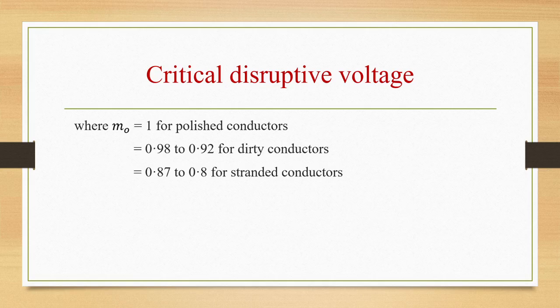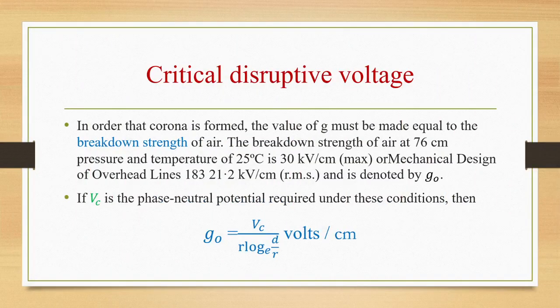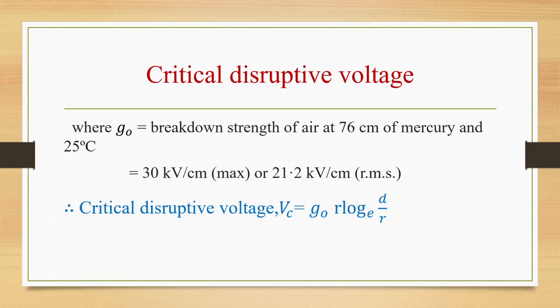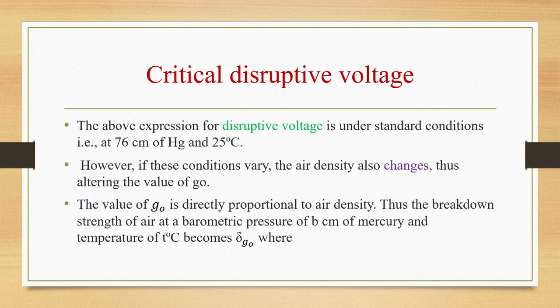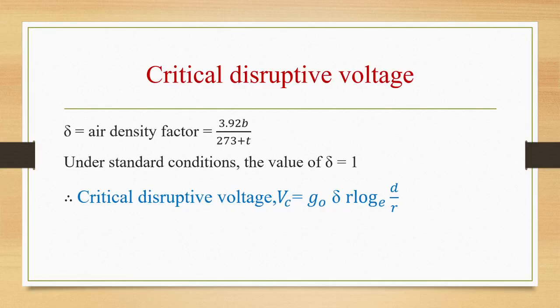If Vc is the phase neutral potential required under this condition, then g naught is equal to Vc by r log base e d by r. Here g naught is the breakdown strength of air at 76 centimeter of mercury and 25 degrees centigrade of temperature, and that is equal to 30 kilovolt per centimeter maximum or 21.2 kilovolt per centimeter RMS value. So the critical disruptive voltage is g naught r log base e d by r. Then we take into consideration the air density factor delta, given as 3.92 b by 273 plus t, and for standard condition it is equal to 1. So Vc has now become g naught delta r log d by r base e.